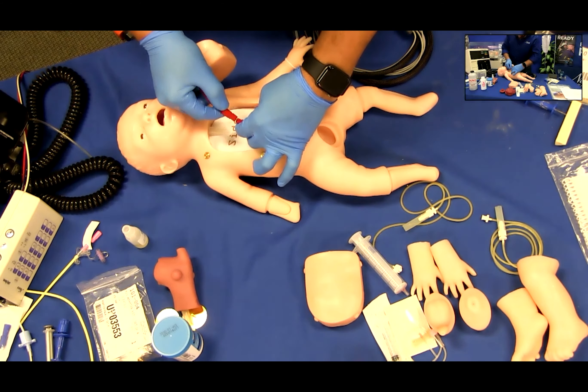To install the defibrillation chest insert and connect the interactive ECG simulator, remove the wire from under the white plate in the base of the chest cavity. Please note that the white plate is adhered to the body of the simulator and removal of the plate should not be attempted. Connect the wire from the defibrillation chest plate to the wire extending from the base of the chest cavity. Then screw the round defibrillation adapter posts into the defibrillation chest skin and into the post site on the posterior of the simulator.